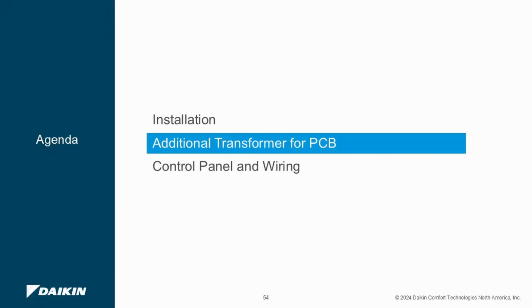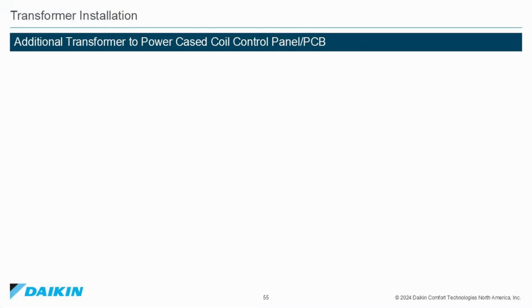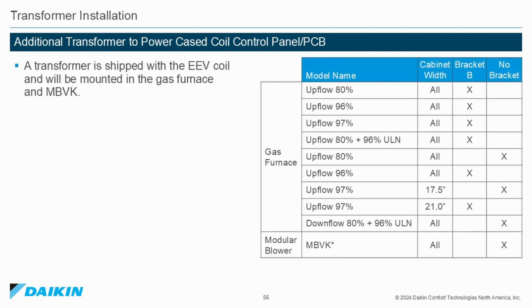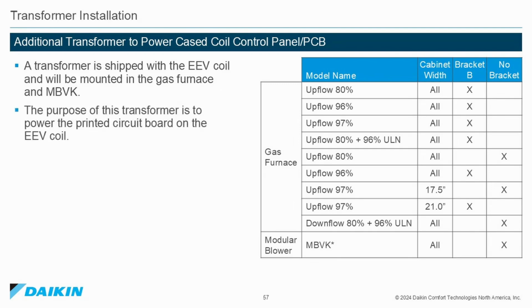Additional transformer for the printed circuit board. Transformer installation. Additional transformer to power cased coil control panel PCB. A transformer is shipped with the EEV coil and will be mounted in the gas furnace and the MBVK modular blower. The purpose of this transformer is to power the printed circuit board on the EEV coil.